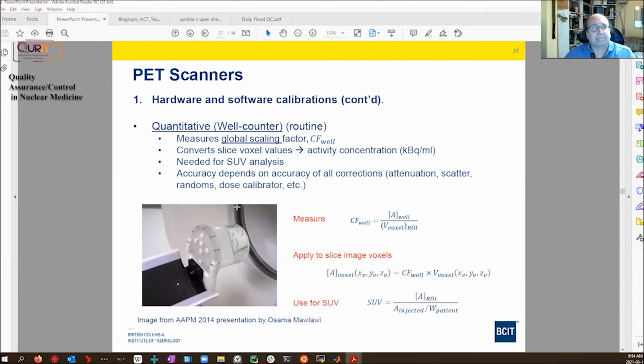I've got to hurry up a little bit. Another calibration is measuring the relationship between voxel values of a reconstructed slice and activity concentration, so that you can recalibrate these voxel values into kilobecquerels per mL. This is done by putting in a cylinder with known activity concentration. You use the well counter dose calibrator to measure the activity. This gives you a global calibration factor between the voxel values and the kilobecquerels per mL that you can apply. That is necessary for the SUV, which requires the voxel values to be calibrated in activity concentration. It's only useful if you've done attenuation, scatter, randoms corrections, etc. So it's very important for PET SUV.